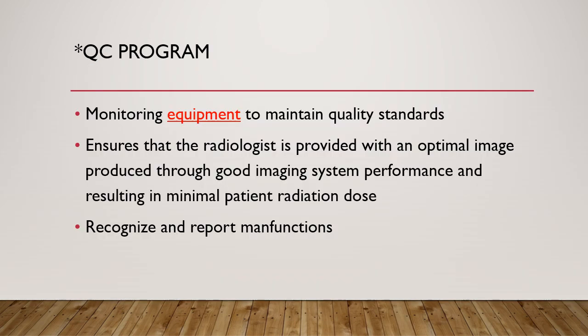On the QC program, which again is quality control, it's about monitoring equipment to maintain quality standards. It ensures that the radiologist is provided with an optimal image produced through good imaging system performance and resulting in minimal patient radiation dose. We want to recognize and report malfunctions also.